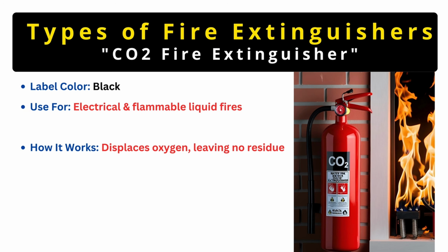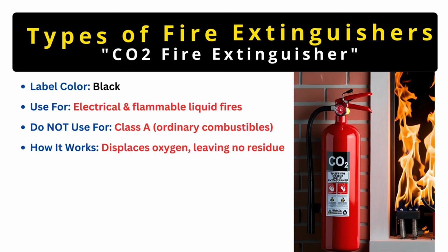But here's the downside: it's not great for ordinary fires like wood or paper. Why? Because while it removes oxygen, it doesn't cool the material enough, meaning the fire could reignite once the CO2 dissipates. So remember, black label for electrical and liquid fires only.